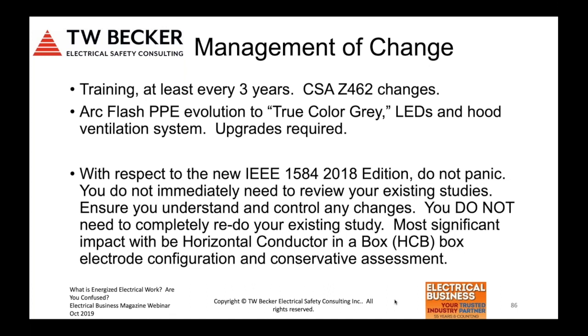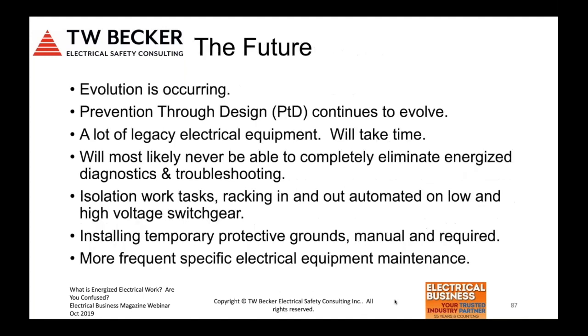Do not panic. You do not immediately have to review your existing studies and update them. Ensure you understand and control any of the changes, any of the information that's provided to you by the consulting engineer that will be contacting you to advise you that you have to update the study. You do not need to completely redo your existing study. Most significant impact will be the horizontal conductor in a box electrode configuration, and conservative assessment, because the incident energy could go up as much as 200%. So manage change throughout this journey that we're all on, and I hope that we continue down this path. But I'm encouraging you to ensure that you have documentation in place, you ask and get answers that can be substantiated by the person that you're asking the question to.